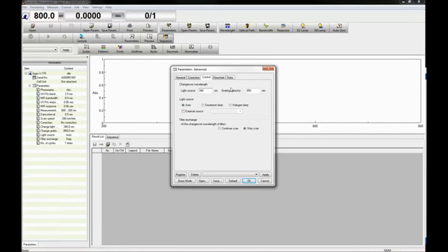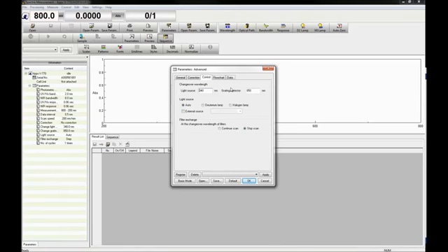If you have a peak at 340 nanometers, you can move that changeover wavelength between 330 and 350 nanometers. The grating detector changeover wavelength occurs at 850 nanometers and can be moved between 750 to 900 nanometers.